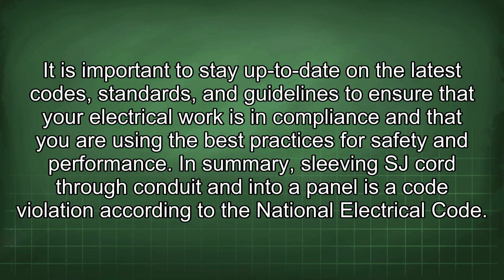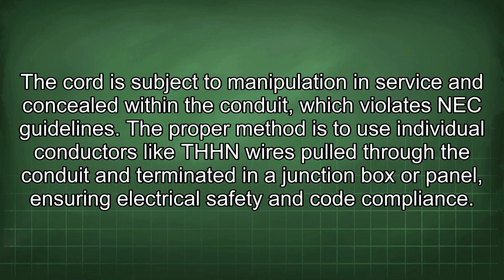In summary, sleeving SJ cord through conduit and into a panel is a code violation according to the National Electrical Code. The cord is subject to manipulation in service and is concealed within the conduit, which violates NEC guidelines. The proper method is to use individual conductors like THHN wires pulled through the conduit and terminated in a junction box or panel, ensuring electrical safety and code compliance.